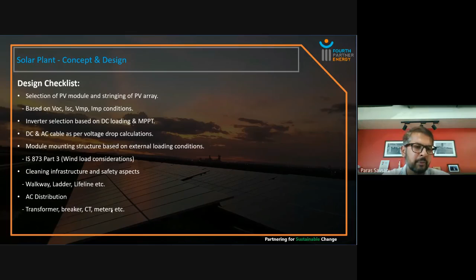Then AC distribution also needs to be planned, like whatever type of distribution has been planned. AC distribution - if HT side termination is there, then a transformer is also required. If there is only LT side, then directly breaker, CT, and meters can be designed.